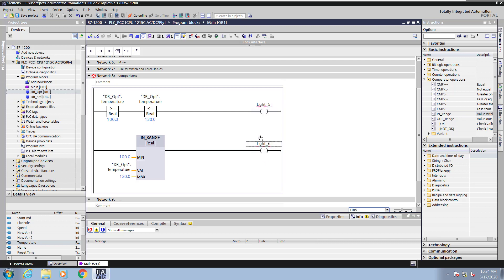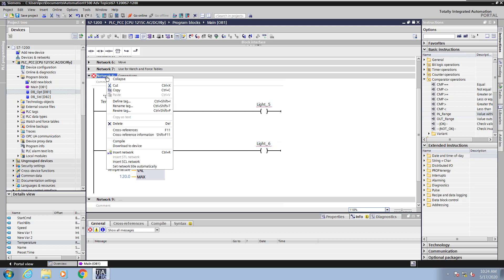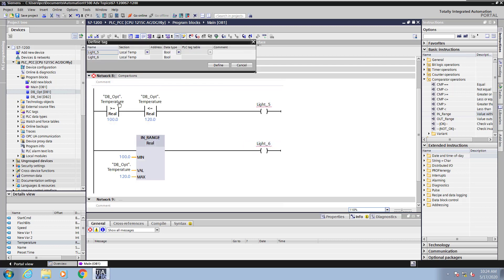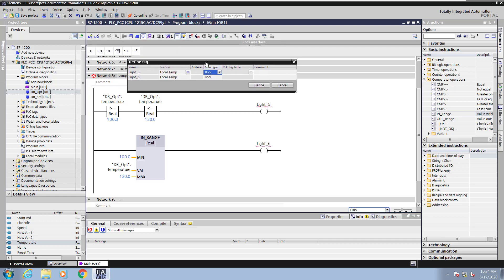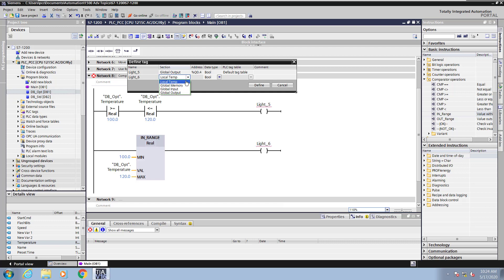I could individually right click on a tag and do define tag, or I can just right click on the network and select define tag and all undefined tags will be listed in the define tag dialog. The first thing is the section where I want to define these tags. It's going to be in the global output area. So I'll take the next available output address for each definition.